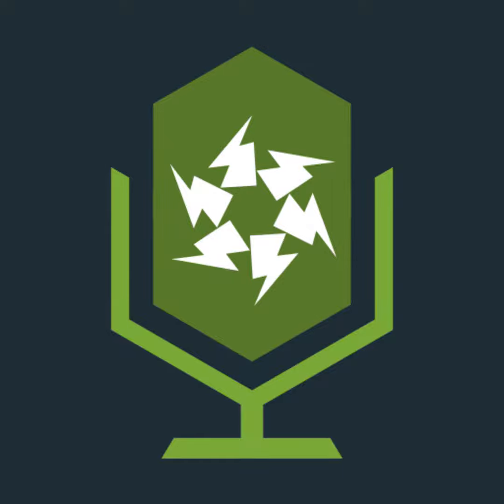Describe the process for selecting the protective device. Well, again, IB, IN, IZ. So IB is the design current. We then would select the protective device, which must be equal to or greater than the design current. If it's not greater than or equal to the design current, then whilst that design current is under normal considered load, the protective device may be overloading. So it needs to be greater than, and that's as simple as that with that one.